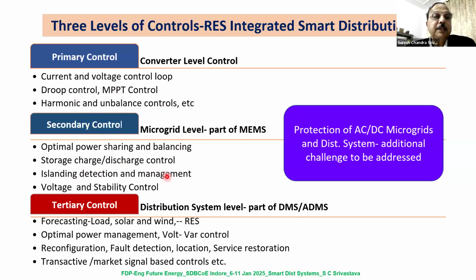Islanding detection and management is required. Voltage and stability control is required. These are some of the controls I have listed. So that is called microgrid energy management system, local microgrid control center. By distribution level, where a lot of microgrids are interfaced, a lot of renewables and the storage is interfaced, you need distribution management system. So you might have seen the distribution and some of the utilities, they have their control center, SCADA center. So they have distribution management system.